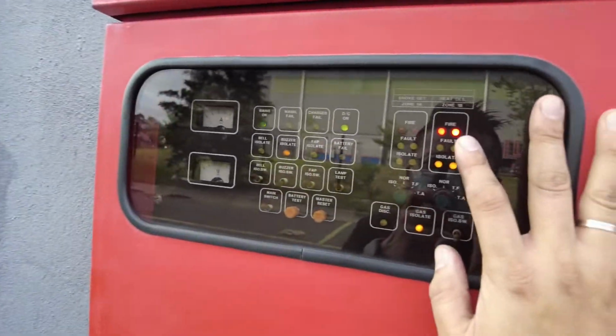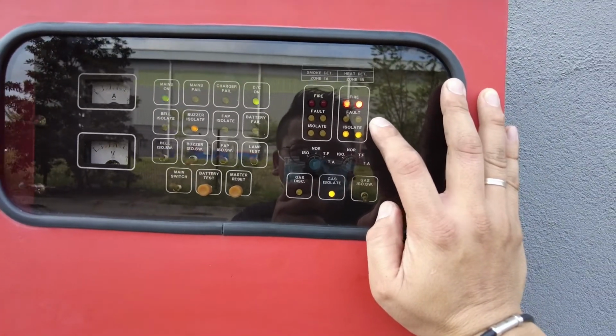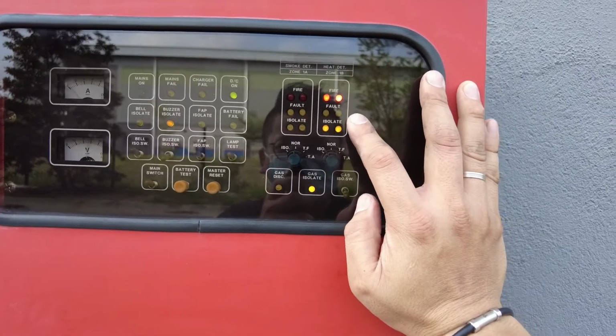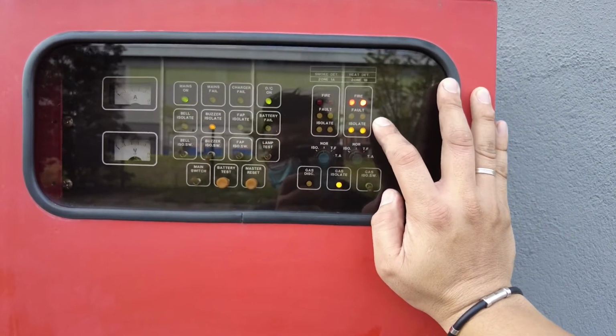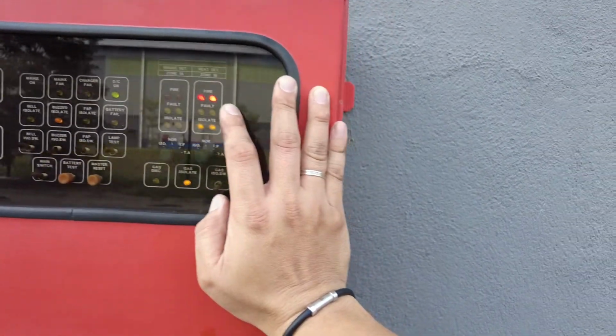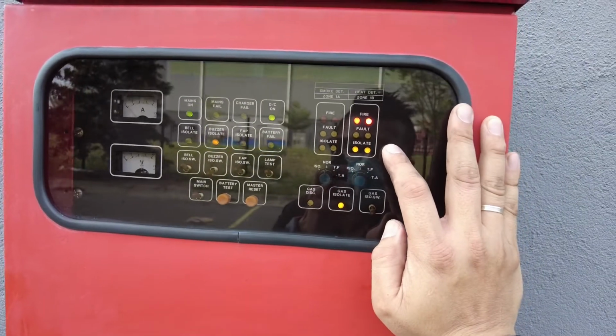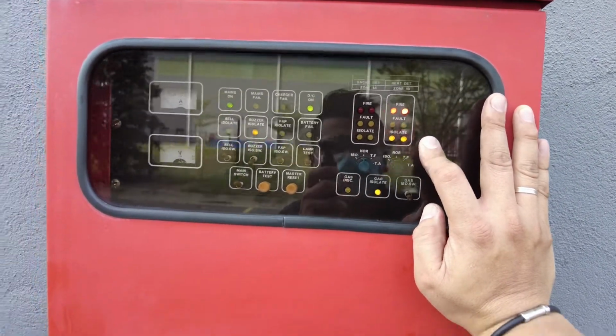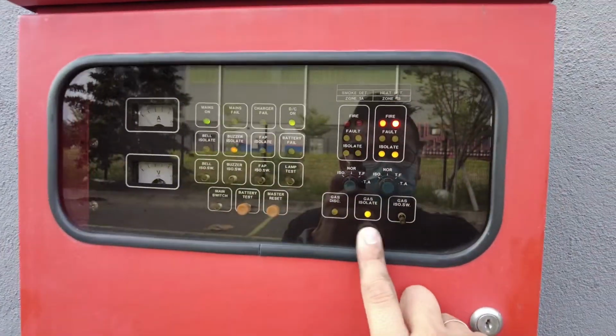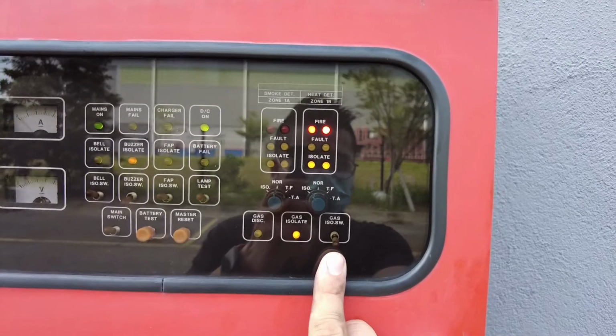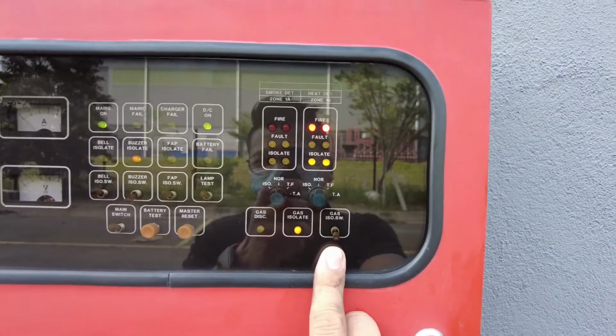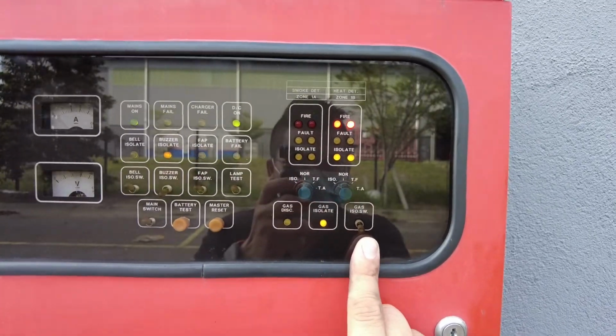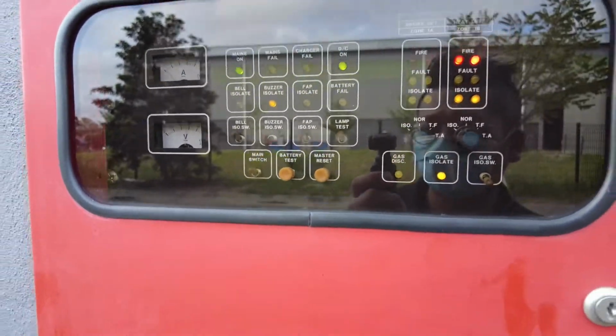Here we have a fire signal. As this fire signal comes in, there could be a possibility the sensor is faulty, the heat detector is faulty, or there's a mistrigger. So you have to isolate it or inform the maintenance people, I mean the firefighting contractor, to look into it. This is the gas isolate indicator light. This is the gas isolation switch. By regulations, whenever you go inside the switch room, you must isolate the gas. But by norm, we like to practice convenience. So make it a habit if possible.